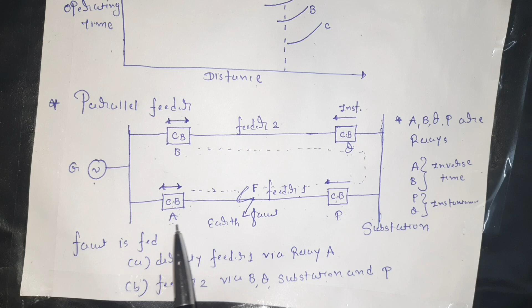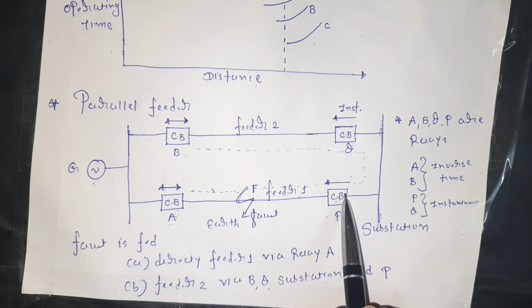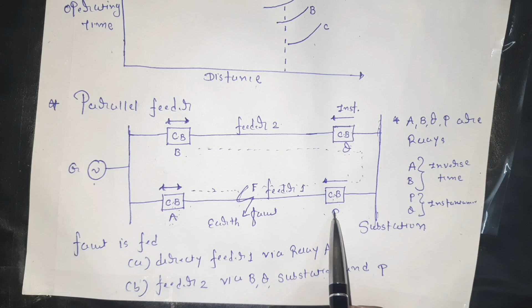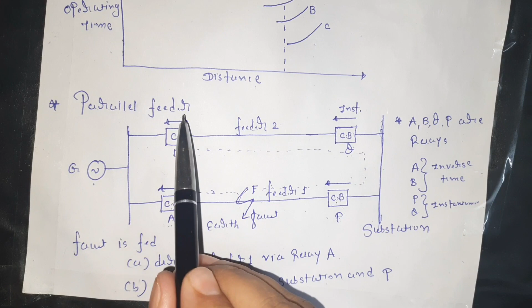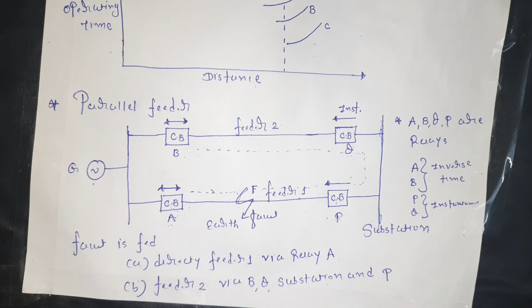But still the fault is fed through A. So the relay at A will operate and the circuit breaker will be tripped. So this circuit breaker and this circuit breaker of the faulty feeder will trip. Thus the faulty feeder A and P is isolated and the healthy feeder BQ will remain in the circuit. This is the way how we can achieve protection of parallel feeder using non-directional as well as directional relays.